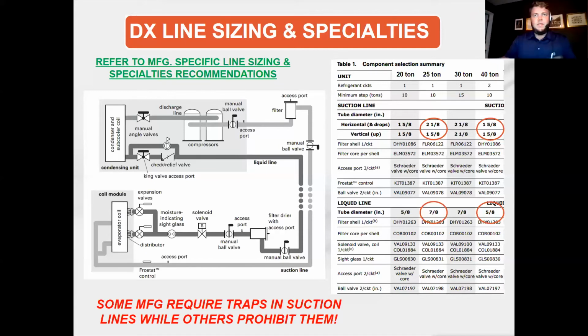No matter what, if they're within this realm of acceptable distance, there's only a single set of line lengths needed for all of those cases in between. So, for example, if we had a 25-ton unit, on the suction line you would want to put in a 2 1/8 inch suction line for your horizontal and drops. But note, in some cases, on the vertical riser, where again, as we talked about, it's important to ensure that the oil is entrained in the gas and returns to the compressor, such as here, you would downsize that vertical suction line to 1 5/8 inches. Then with the liquid line, 7/8 across the board.